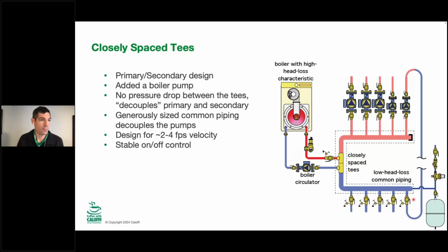So if for whatever reason we had that expansion tank connected over on the blue line on the boiler, which would be fine on the suction side of the boiler, then the boiler is the primary loop. In this picture right here, I would explain that your distribution side is the primary loop because that's the point of no pressure change connection in the system. And that goes way back to the B&G days. He's the one who said, well, if we're going to do primary, secondary, we need to explain which is the primary loop. And that was the explanation, which makes sense. I mean, wherever you put the tank is the point of no pressure change. That would be the primary loop, regardless if the boiler's in it or not.